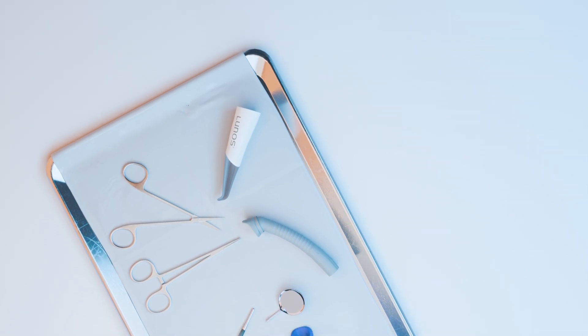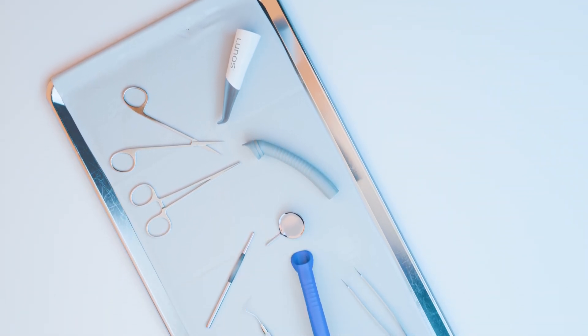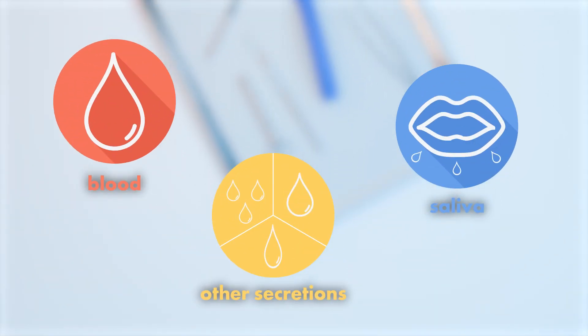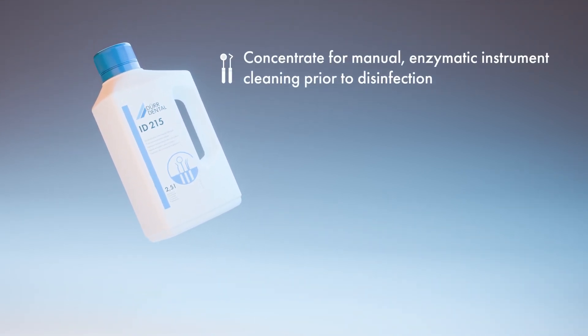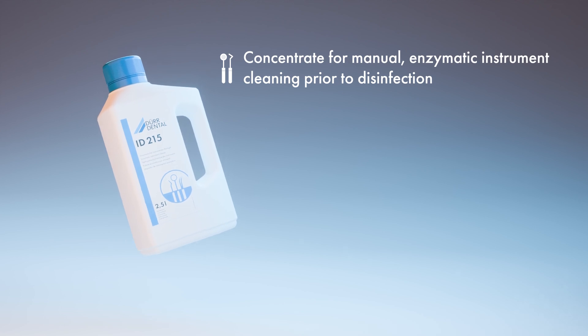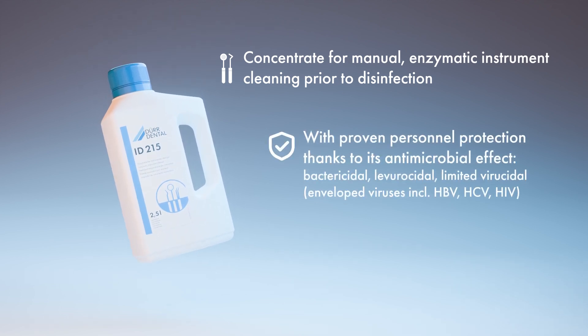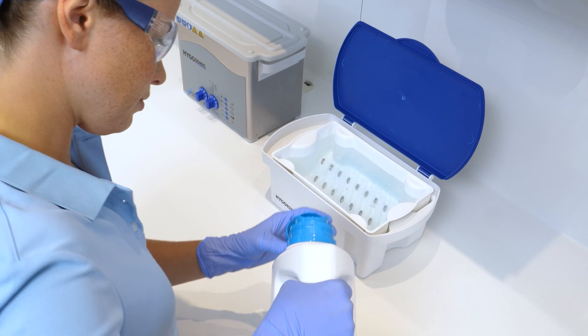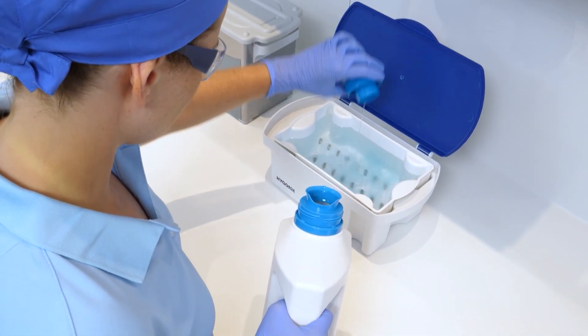The objective of these measures is residue-free cleaning to avoid impairing the following disinfection and sterilization steps as a result of organic residues. Due to the potential risk of injury and infection, we recommend using a disinfecting cleaning agent. Cleaning solutions must be freshly made every day and replaced immediately in case of visible contamination.